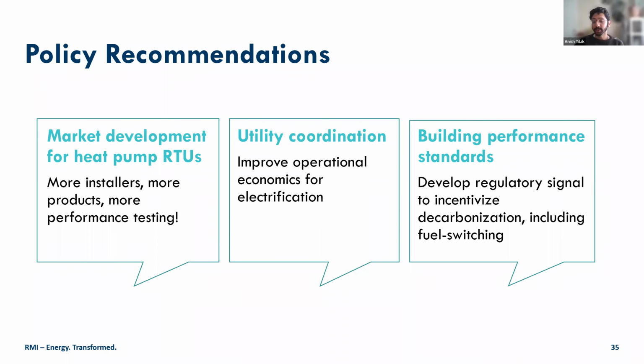And I'll just say we initially tried to test that retrofit case using VRF because that is more well understood and applied in the commercial market. But the cost of those retrofits was significantly higher than what we're presenting here, which is a one-to-one replacement. Everything's packaged. So we are trying to balance what the market's comfortable with and whether those are slightly more energy efficient than an all air system, but also the first cost and the real challenges of retrofitting an existing building.